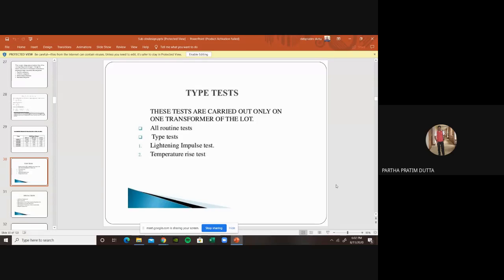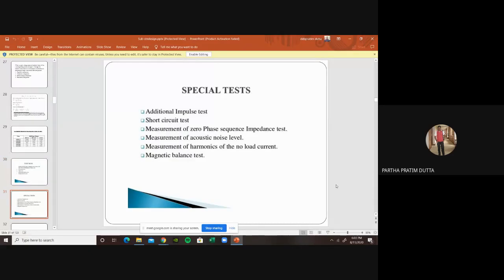In the type test, we include all the routine tests I already mentioned. Certain type tests we do are the lightning impulse test and the temperature rise test, which I will discuss. And some special tests we do are the additional impulse test, short circuit test, measurement of zero phase sequence impedance test, acoustic noise measurement test, measurement of harmonics of the no load current, and so on. Time will not permit to discuss all these, so I will skip them.